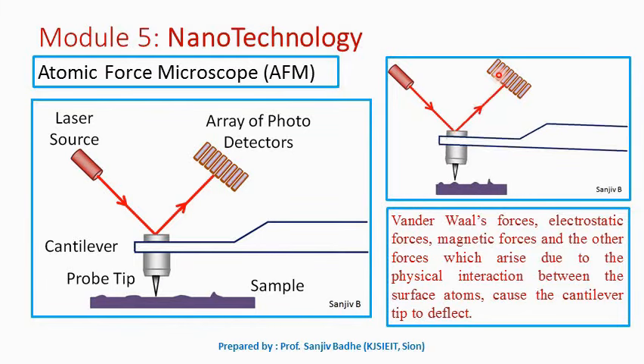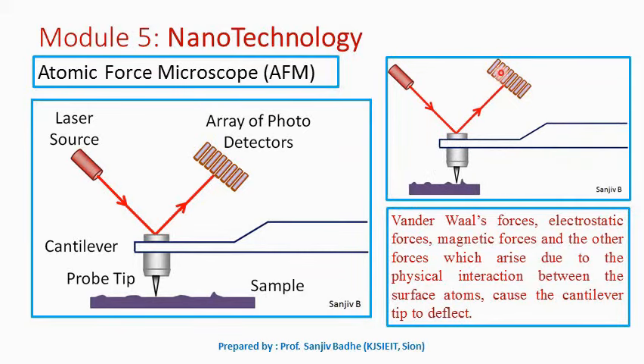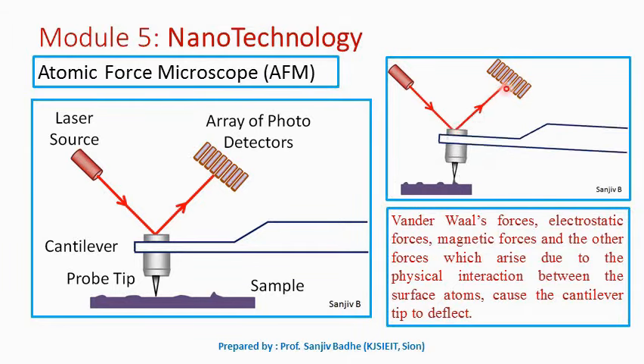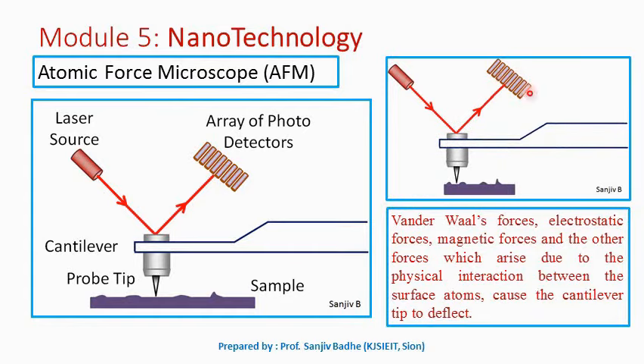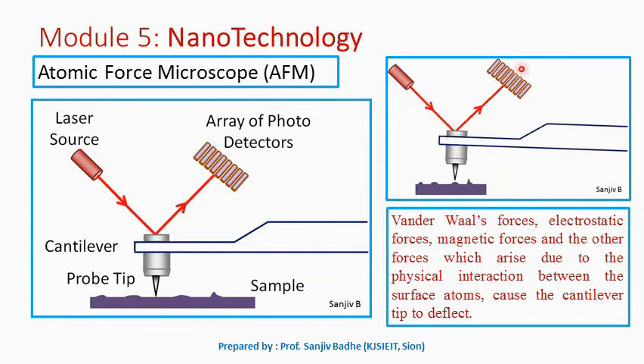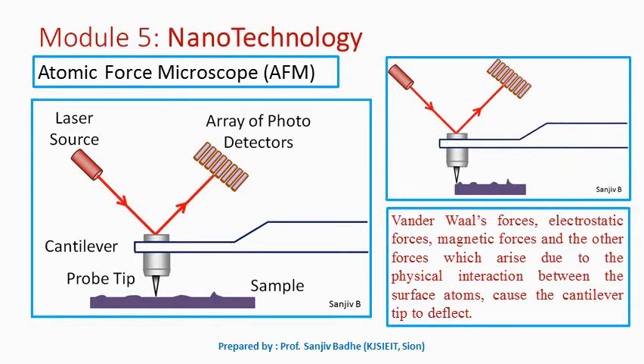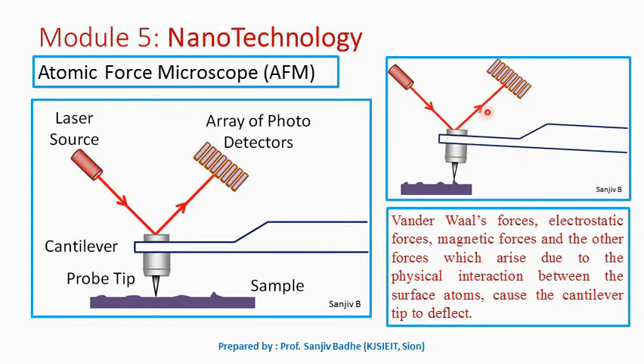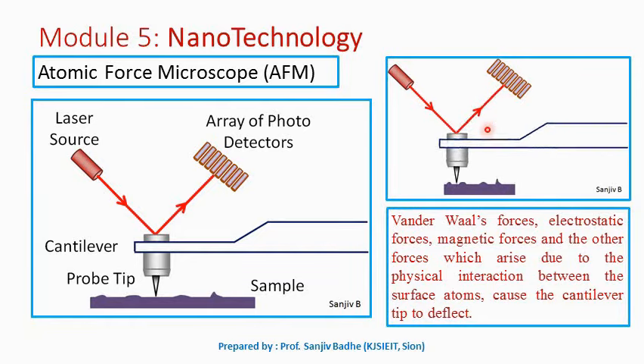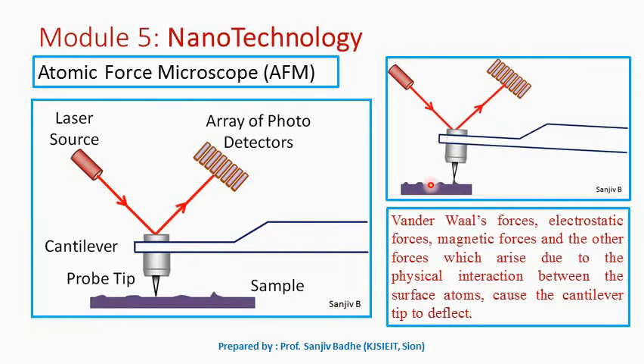Accordingly, the reflected light rays will be collected by different photodetectors in the array. We can find the amount of deflection produced in the reflected laser beam by analyzing which photodetector is collecting that particular laser beam. This analysis can be done with the help of computer-controlled devices, and analysis of this deflection will help us in producing a 3D image of the sample surface.